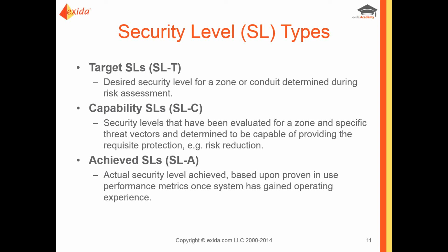If the equipment is not up to the security level that you need, or if they have threat vectors that it's just really not possible for them to come up with a security level capability from within the hardware, then this is where it's important for the security manual to let you know what additional countermeasures, alternate means of risk reduction need to be put in place that would be the end user's responsibility to be able to have the security level capability for that zone in total.